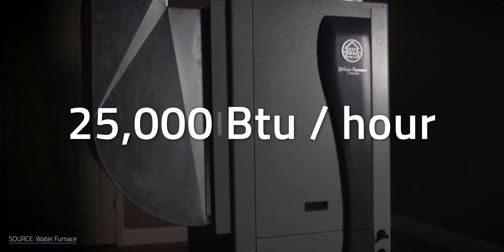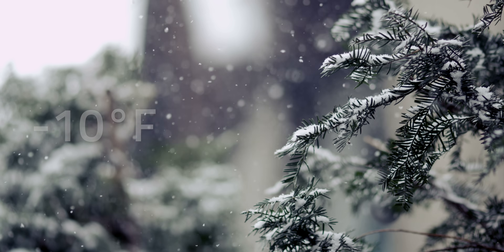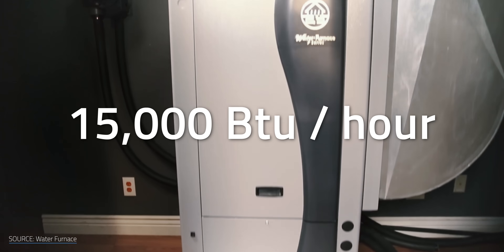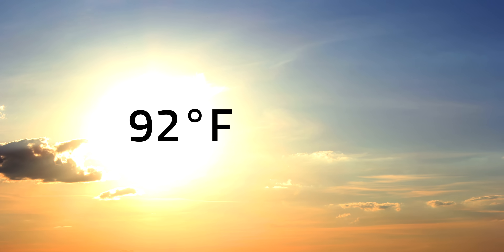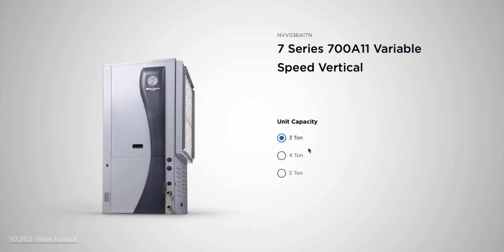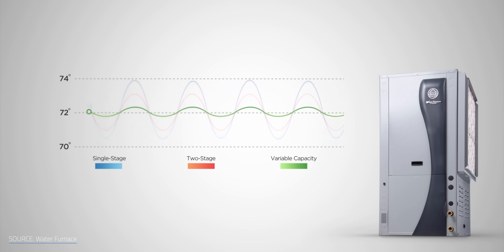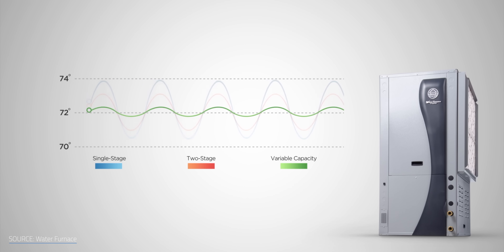The independent designer calculated that we'd probably need about 25,000 BTU per hour for heating on the coldest days — around negative 10 degrees Fahrenheit or negative 23 degrees Celsius — and 15,000 BTU per hour for cooling in summer on the hottest days, around 90 degrees Fahrenheit or 32 degrees Celsius. Ideally we'd have a 2-ton system, but since we went with the Water Furnace Series 7, the smallest available is a 3-ton system. The fact it's a little oversized shouldn't be an issue since it's a variable speed system that can run partial load demands, and it might actually make for even quieter operation.